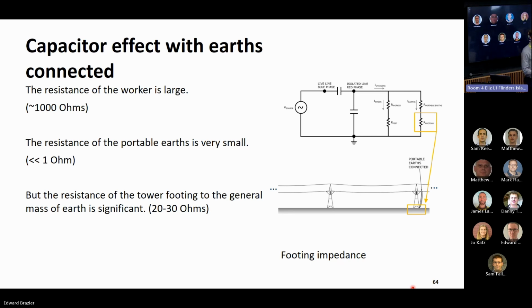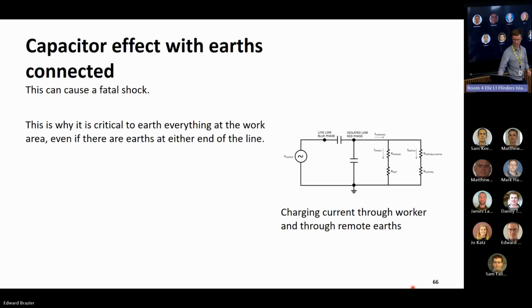So this has a big impact. If the resistance of the worker is 1,000 ohms, consider the current splitting between those two paths: some goes through the worker, some through the portable earths. It means the amount through the worker can actually be significant, enough to cause a fatality. That's one of the reasons it's critical to earth everything at the work area, even if you've got remote earths at the other end of the line.